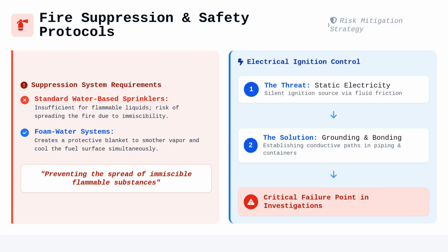The complexity of storing these materials extends to the fire suppression systems that we rely on when prevention fails. Standard water-based sprinklers are rarely sufficient for large quantities of flammable liquids because many of these substances are immiscible with water and would simply spread the fire if handled incorrectly. Instead, we look at specialized suppression densities that utilize foam water systems, which create a blanket that smothers the vapor production and cools the fuel surface simultaneously.